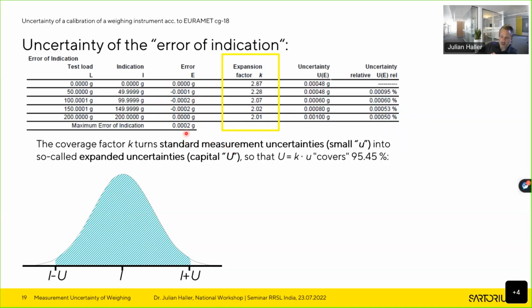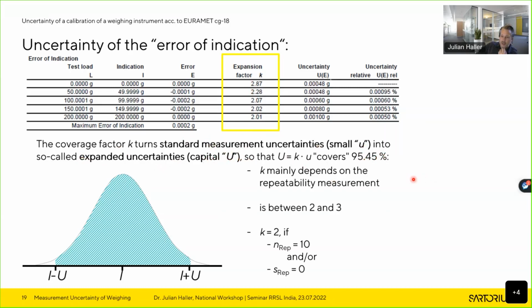And of course, 68% is not sufficient. So what is done by convention actually is that so-called expanded uncertainties, which are then given with a capital U, are stated so that it covers 95.45%. And to do that, you have to calculate the expansion factor. And I'm not going into detail because that's again a quite complicated formula. The Welch-Satterthwaite formula, again, also given in the CG18, also in the GUM, if you want to have a detailed look at that. But just to explain that, k does not always equal 2, which is a misconception that is given in many cases where k equals 2 is assumed always. But you really have to calculate that based on the measurement results.